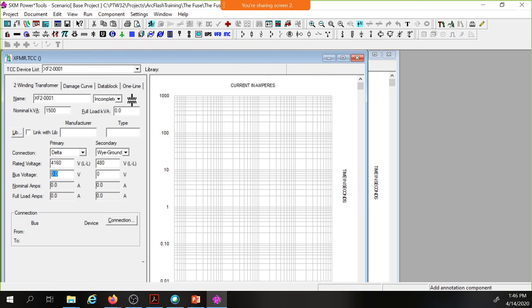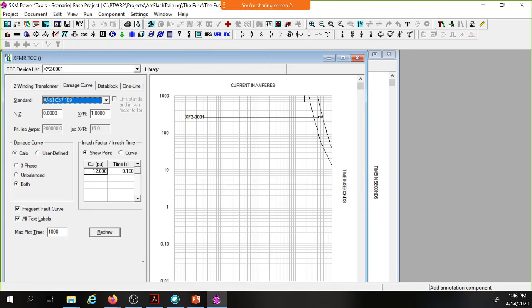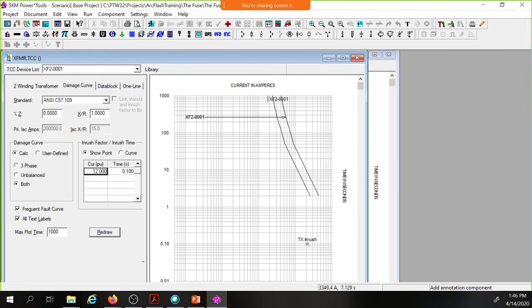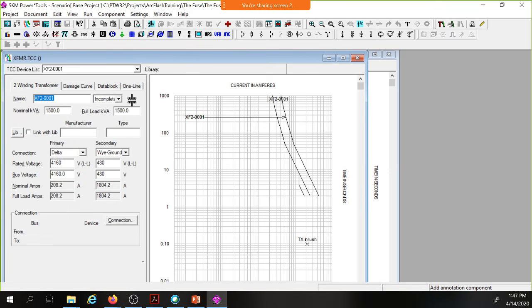Bus voltage on the primary is 4160. Since I'm just going straight into this, I'll have to enter it; a lot of times your bus will automatically populate that. And there's your transformer damage curve. I'll do this times 1. So there's my damage curve. I have to give it a percent Z. I don't know, 5.75 sound good to everybody? I'll change that to about 6. Hit redraw. Okay, so there's my transformer damage curve, for a two winding transformer.